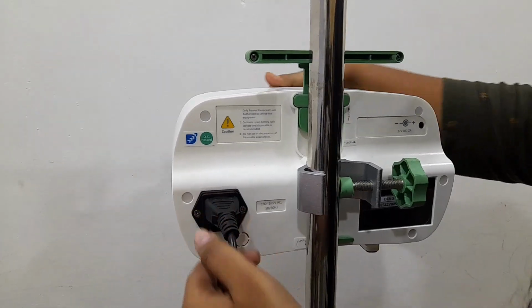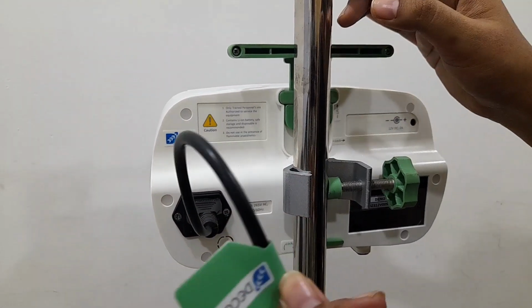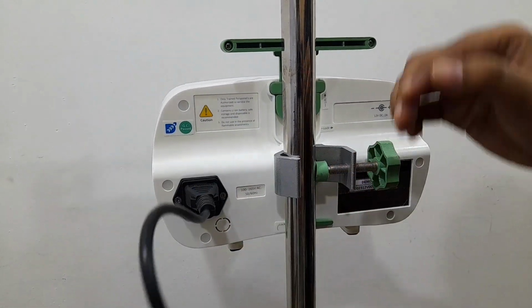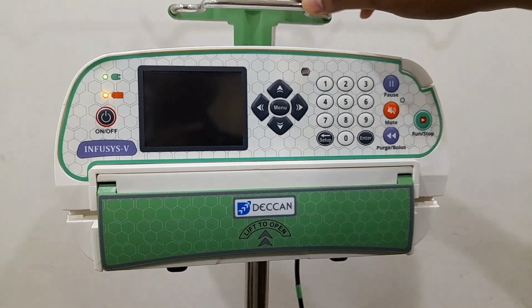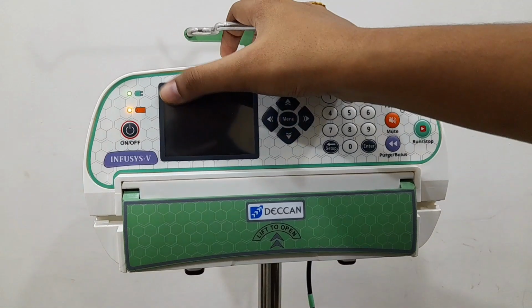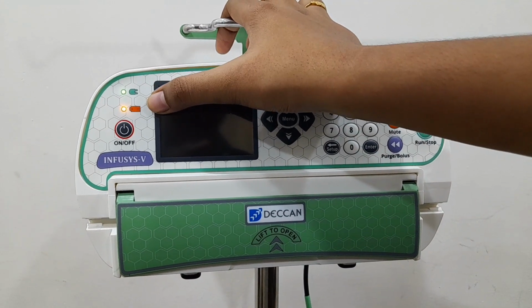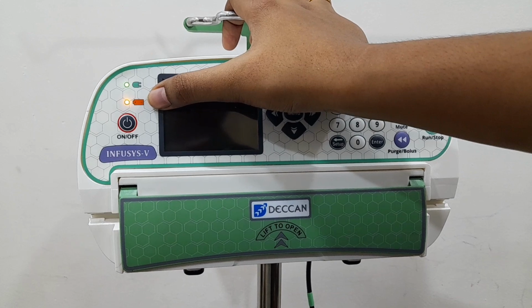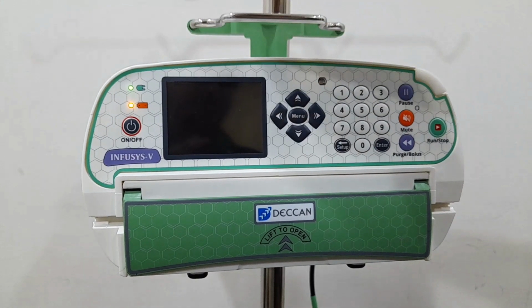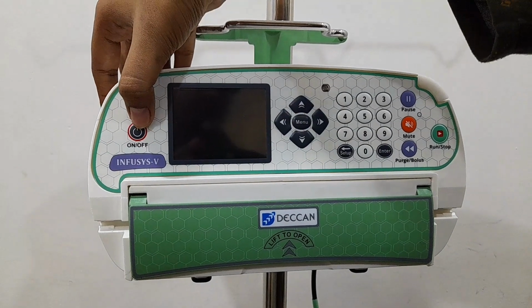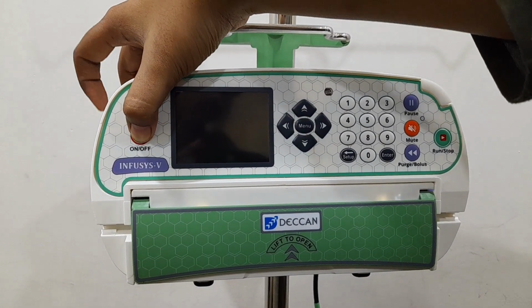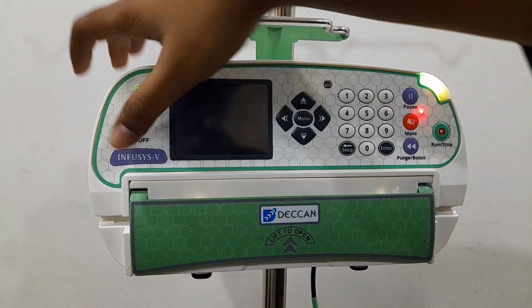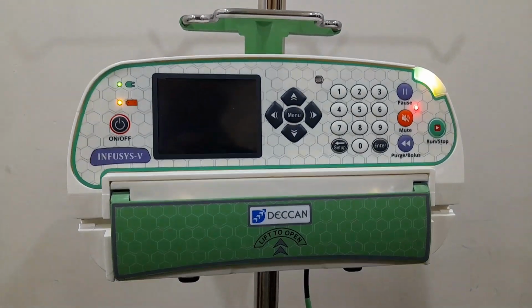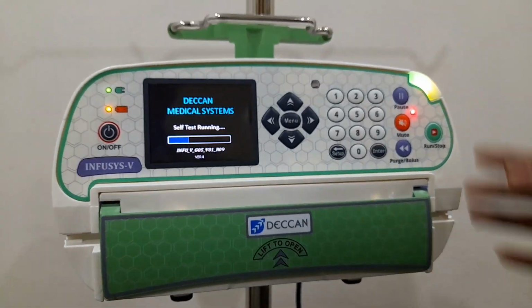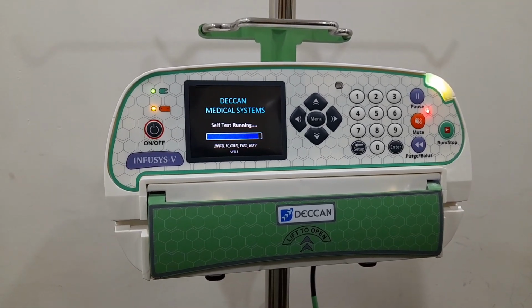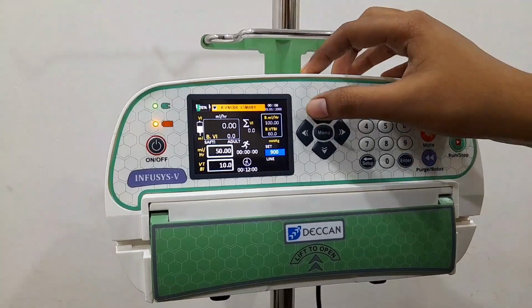Plug the power cord to AC mains, and you can notice the power cord tag here with the warning symbol. After the power cord is connected with AC mains, we can see the LED indications in the front panel. The green LED indicates that the unit is connected with AC mains, and the orange LED indicates that the battery is charging, and the orange LED gets turned off once the battery is fully charged. Switch on the pump using the on or off key. The unit starts self-testing. Wait until the self-testing has completed. Once the self-testing has completed, RV mode standby will display on the screen.